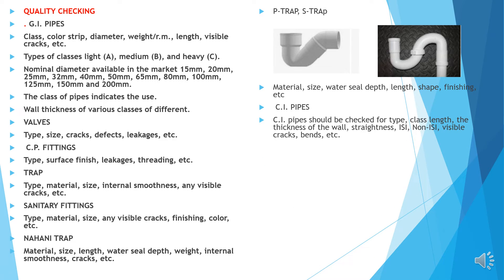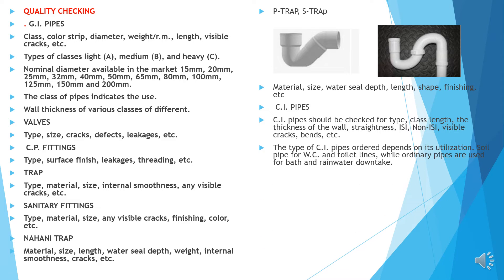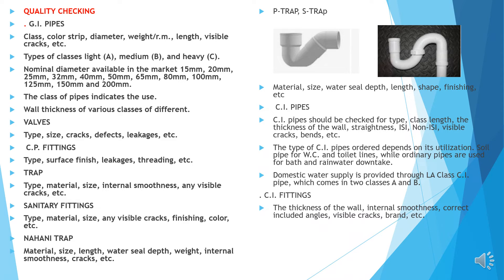CI pipes: should be checked for type, class, length, thickness of the wall, straightness, ISI mark, visible cracks, bends, etc. The type of CI pipe depends upon its utilization — soil pipe for WC and toilet lines, while ordinary pipes are used for bath and rainwater downpipe. Domestic water supplies provided through LA class CI pipe, which comes in two classes A and B. CI fittings: check thickness of the wall, internal smoothness, correct angles, visible cracks, brands, etc.